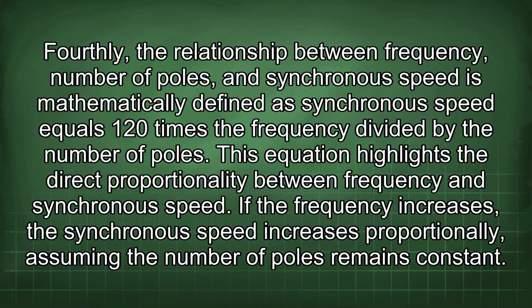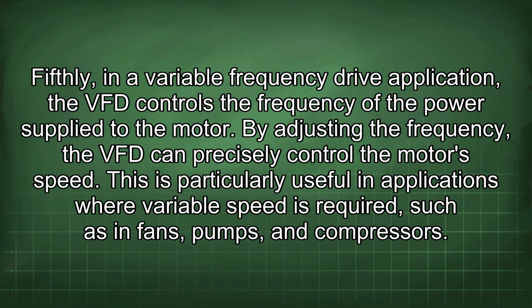Fourthly, the relationship between frequency, number of poles, and synchronous speed is mathematically defined as synchronous speed equals 120 times the frequency divided by the number of poles. This equation highlights the direct proportionality between frequency and synchronous speed. If the frequency increases, the synchronous speed increases proportionally, assuming the number of poles remains constant. Fifthly, in a variable frequency drive application, the VFD controls the frequency of the power supplied to the motor. By adjusting the frequency, the VFD can precisely control the motor's speed. This is particularly useful in applications where variable speed is required, such as in fans, pumps, and compressors.